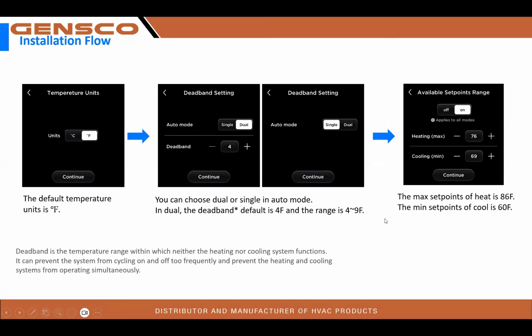Our deadband settings. Also, we can set our max and min on heating and cooling. This is pretty important. I used to set up all thermostats to where the homeowner couldn't lower it down any lower than 66 degrees for obvious reasons. I don't want them to ice up the coil.